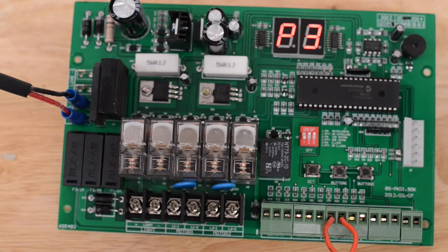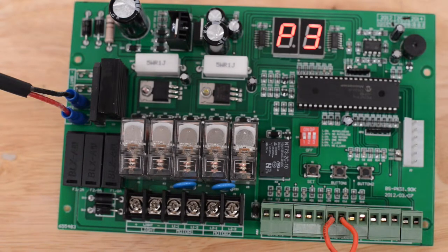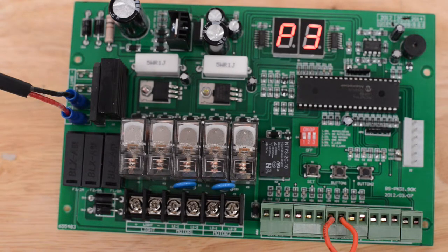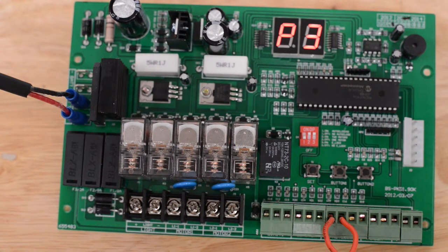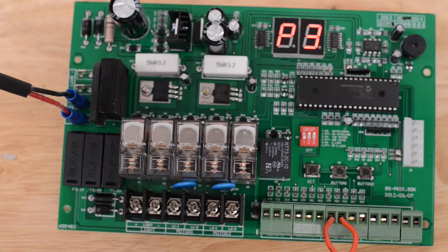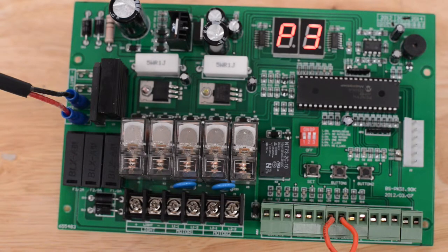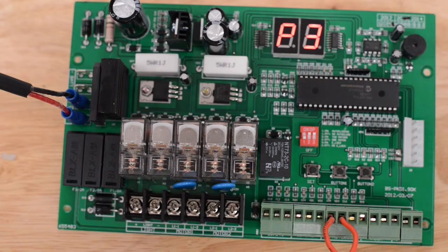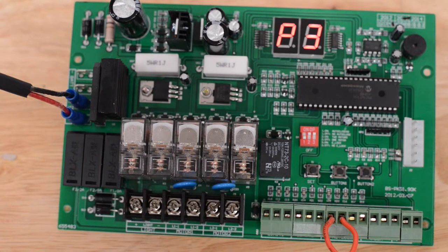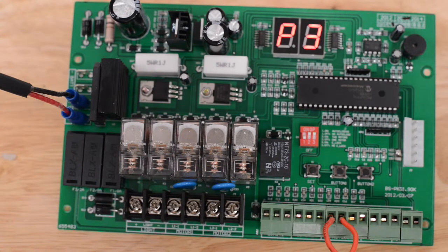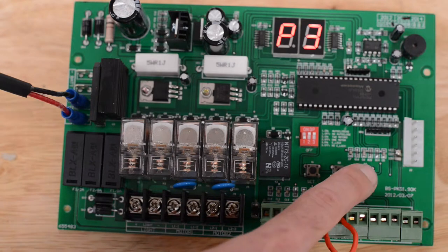If you observe this counting you will know the runtime. You can then set your P1 parameter above that runtime to make sure you have room to make adjustments to the slowdown and then select how many seconds you want it to run fast for before it goes into slowdown mode. Once we've selected your P2 setting, press set to proceed on to P3. P3 is your force setting.